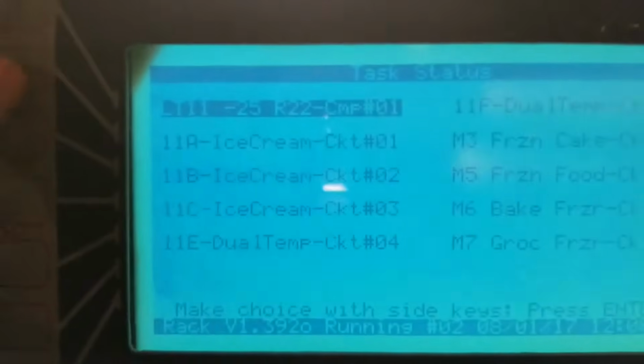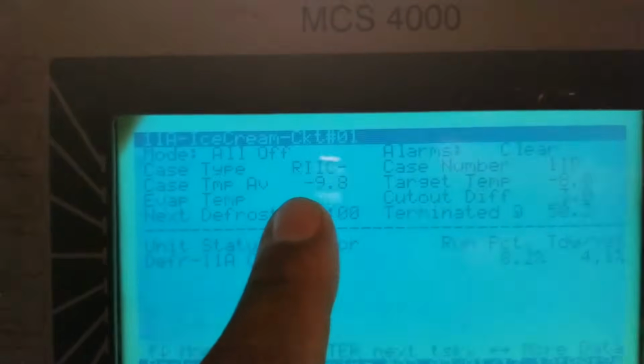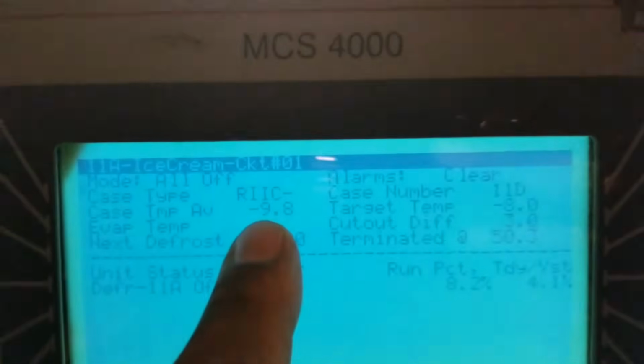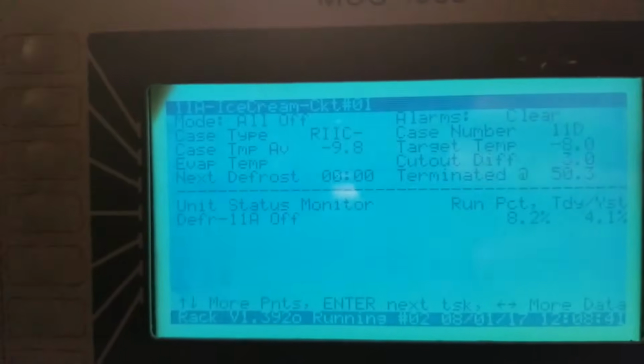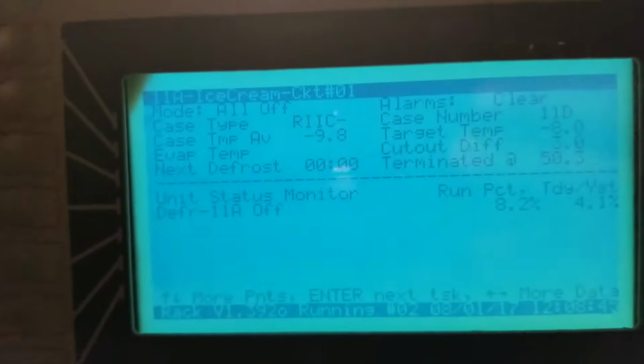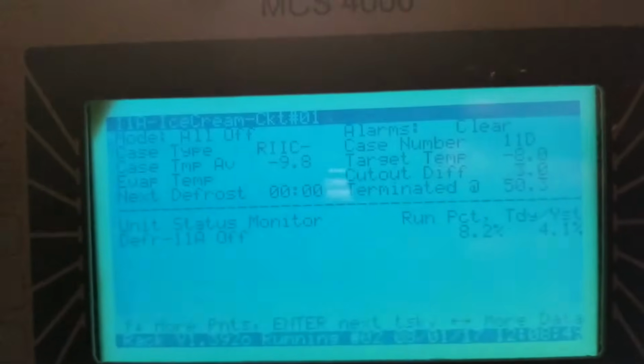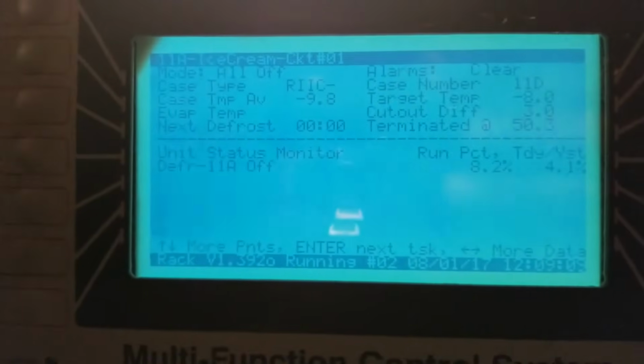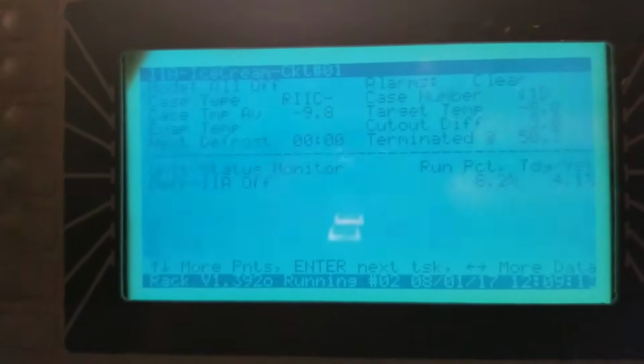So if we go into system 11A, that's reading -9. What I did was, this was reading a lot colder than what it actually was. Let's just say it was reading -9 like it is now, but I took a temperature reading at the case and it was reading -5. So that would cause my compressors to start shutting down because the controller thought it reached its set point. So it was giving a false reading. So I had to calibrate that temperature sensor to what it read on my actual digital Fluke downstairs. So I calibrated this to -5, so now it's actually reading the right temp.